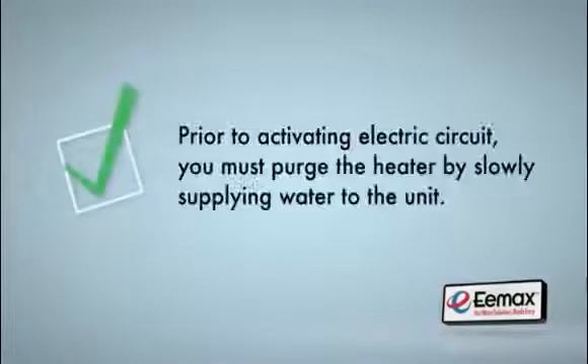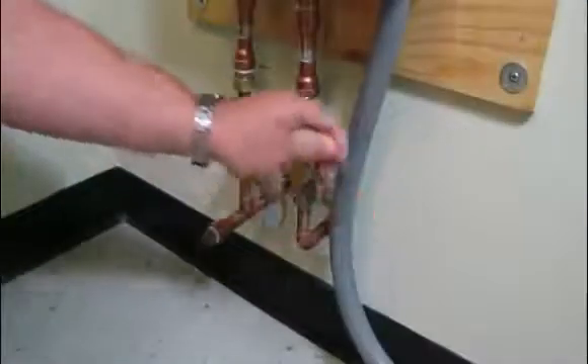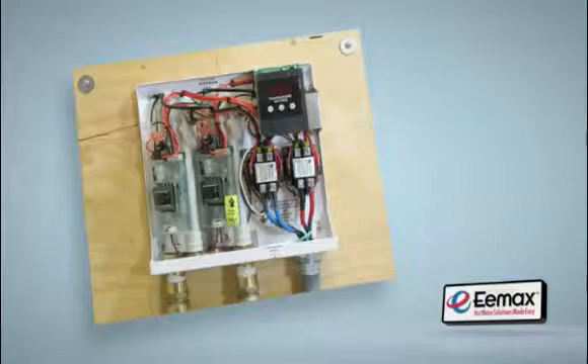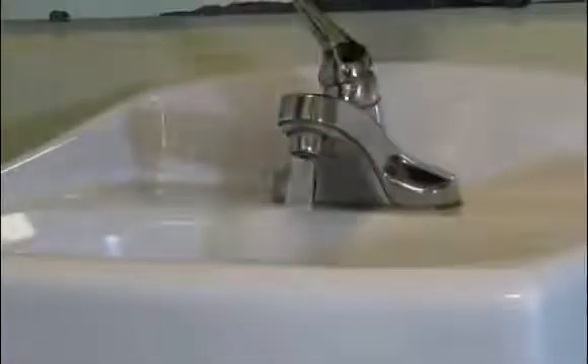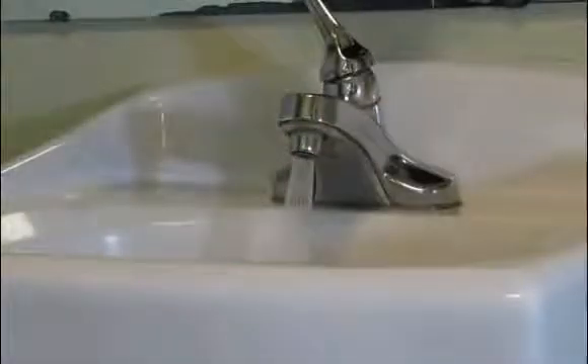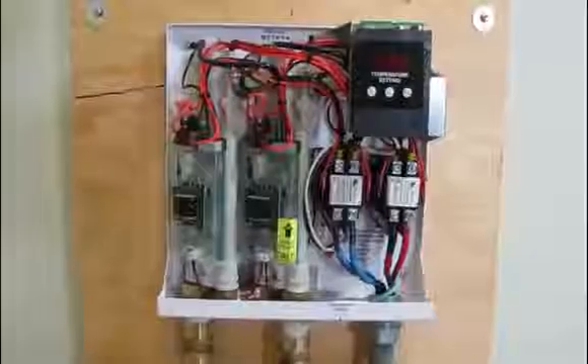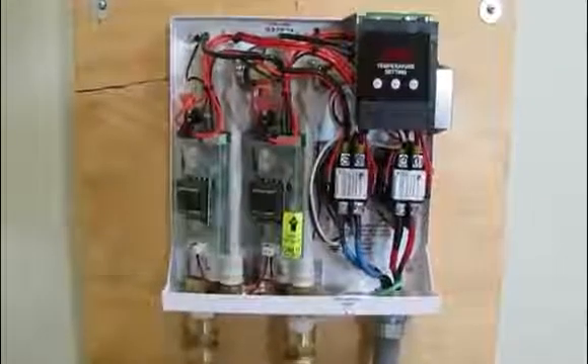Prior to activating the electrical circuit, you must purge the heater by slowly supplying water to the unit. Turn on both valves and let the chambers pressurize with water. Inspect the unit for any possible leaks. Before sending any power to the heater, it's important to circulate water through the unit by turning on any hot water faucet or shower in the home or building that would receive hot water from the Eemax heater. Let the water run for at least two minutes to assure no air pockets are trapped in the heater chambers. If air is caught in the chamber, it's possible the heating element can burn out and fail.